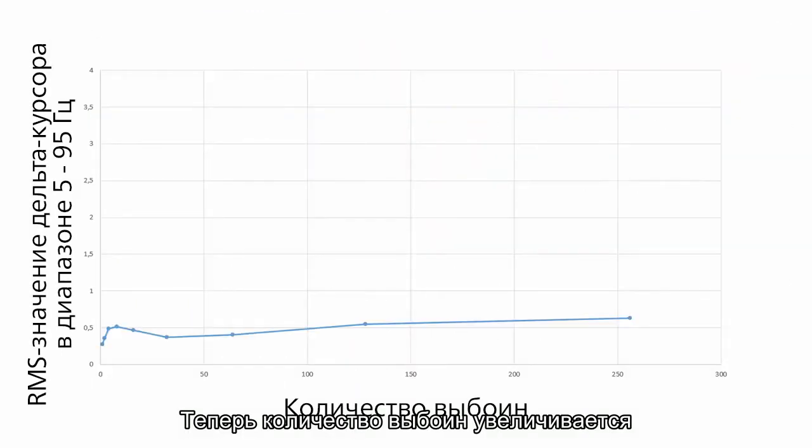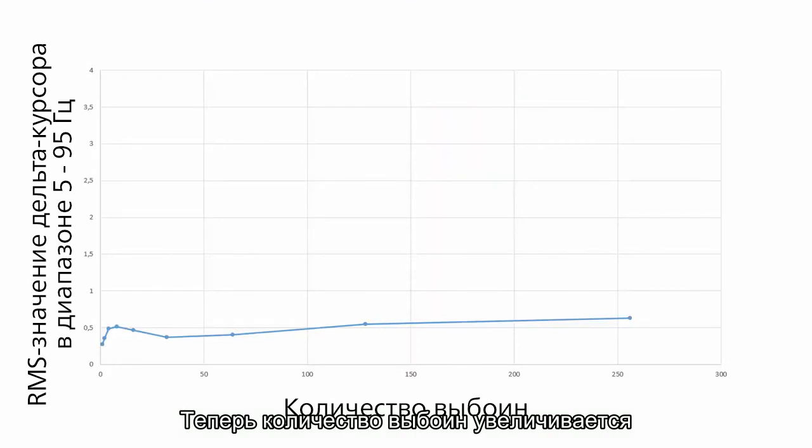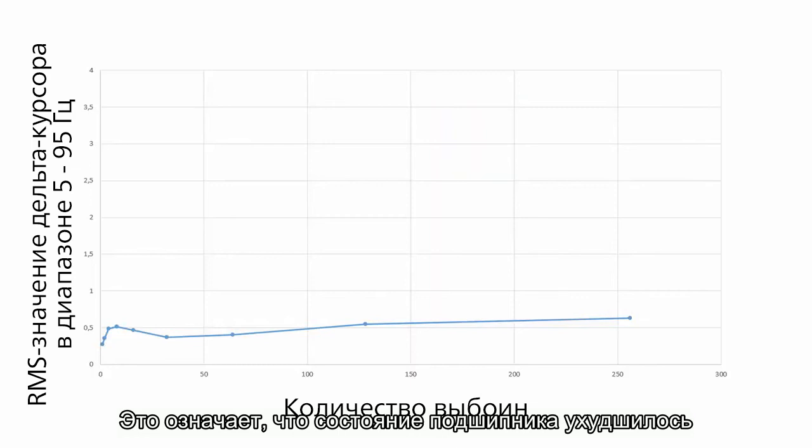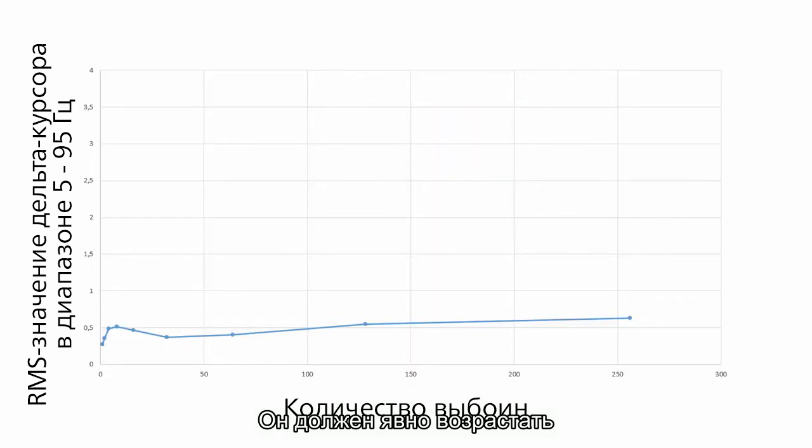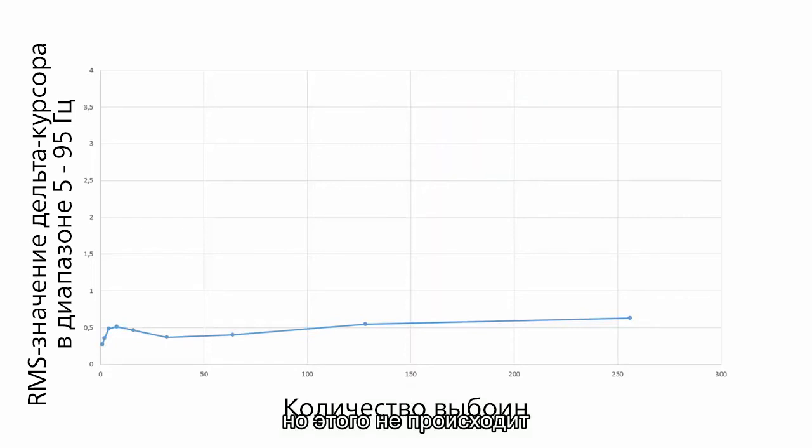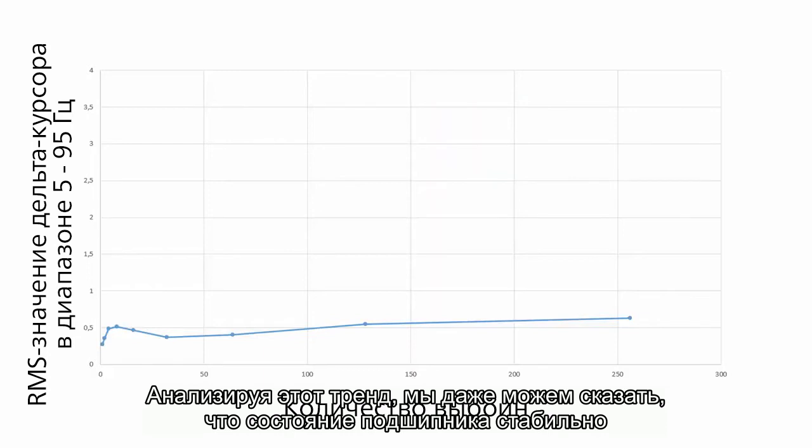Now we are increasing the number of cracks. It means that bearing condition is worse. But look at the trend of delta cursor. It should clearly increase. But it doesn't. When we analyze this trend, we probably say that the condition is stable. I try to explain such weird behavior.